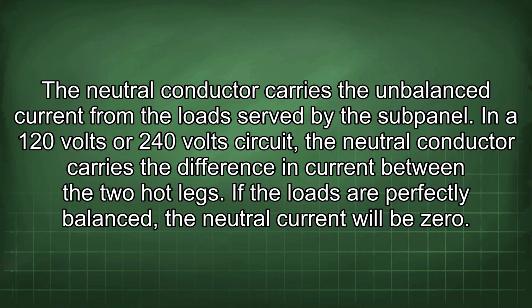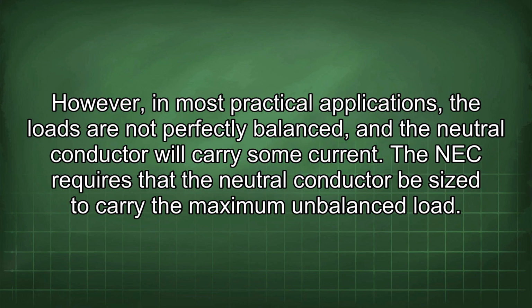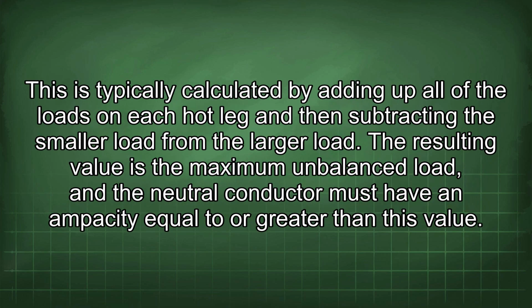The neutral conductor carries the unbalanced current from the load served by the subpanel. In a 120 volt or 240 volt circuit, the neutral conductor carries the difference in current between the two hot legs. If the loads are perfectly balanced, the neutral current will be zero. However, in most practical applications, the loads are not perfectly balanced, and the neutral conductor will carry some current. The NEC requires that the neutral conductor be sized to carry the maximum unbalanced load. This is typically calculated by adding up all of the loads on each hot leg and then subtracting the smaller load from the larger load.